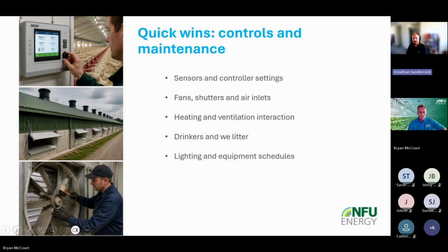Many of the first opportunities shouldn't require major capital investment. It should be just reviewing things such as control sensors, temperature and humidity, checking them against independent instruments to make sure that they're still within tolerances. Some examples: poorly positioned or inaccurate sensors can cause unnecessary heating or ventilation, and purely from repositioning them that could lead to significant energy savings. Ensure that heating and ventilation systems are communicating and working together. We don't want them fighting with each other, wasting energy throughout the year.